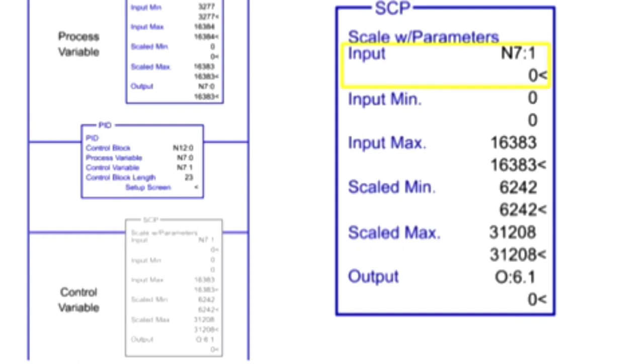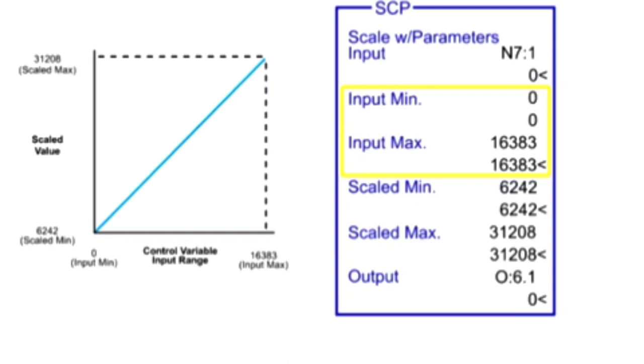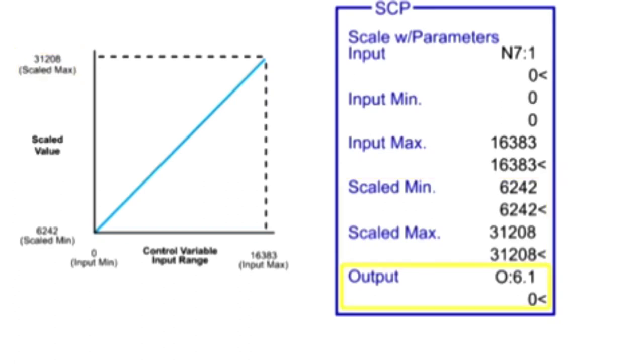The input parameter of the SCP contains the memory address of the PID output values that will be scaled. The input minimum and input maximum are programmed as the smallest and largest values of the input range. The input value is then scaled between the ranges programmed in Scaled Minimum and Scaled Maximum parameters. Scaled Minimum value is programmed as 6,242, representing the low end of the analog output module range. Scaled Maximum value is programmed as 31,208, representing the high end of the analog output module range.